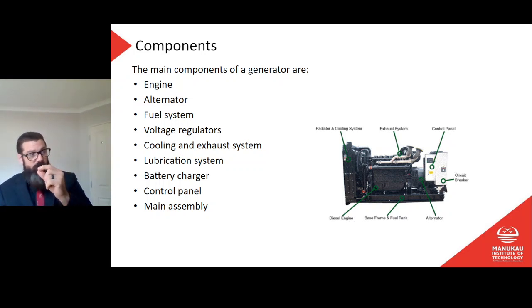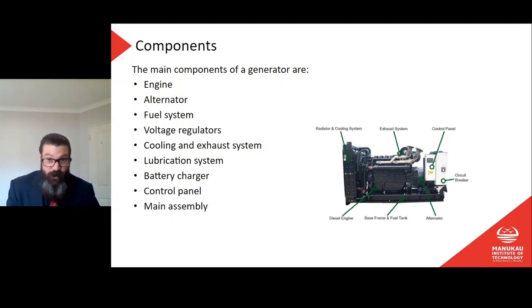And of course the spring was stretched so it wouldn't react fast enough, because the voltage regulator is sensing and sending signals really fast, like multiple times per second. So if the governor's not responding fast enough, then it hunts, because you tell it to speed up, and by the time it reacts, it's going too fast. So you tell it to slow down, and by the time it reacts, it's going too slow. So you get the engine speed, and you'll hear it go, vroom, vroom, vroom. That's called hunting. That's because there's something wrong with that voltage regulator and/or the governor.